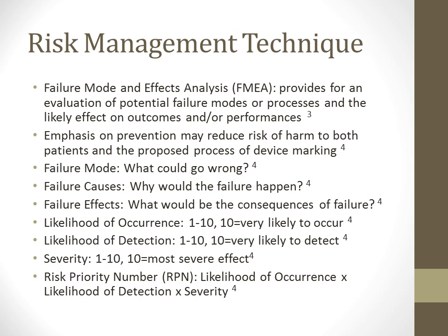The risk management technique that I chose for my project, for this UDI device marking supplier issue, was the FMEA risk management technique, since it is the most common tool used to assess risk management. Most of us are familiar with FMEA because we learned about it in Chapter 6. A failure mode and effects analysis provides for an evaluation of potential failure modes or processes and their likely effect on outcomes or performances. There's an emphasis on prevention and reduced risks with using this FMEA process to reduce harm to both patients and the proposed process of device marking.